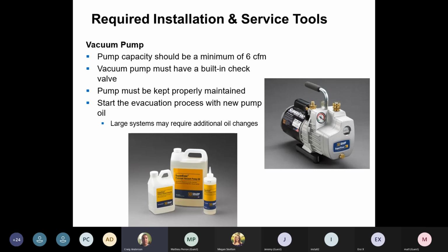So make sure your vacuum pump is working. It has a built-in check valve. Some of the older vacuums don't have a built-in check valve. And what happens if you're not sitting there and watching the unit and the vacuum turns off, if there's no check valve in there, now your vacuum is under a negative pressure. So when it turns off, it's going to suck whatever it can from wherever. So we could actually get the AC that's under a negative pressure to be pulling whatever's in that vacuum pump out. So make sure it's got a built-in check valve.